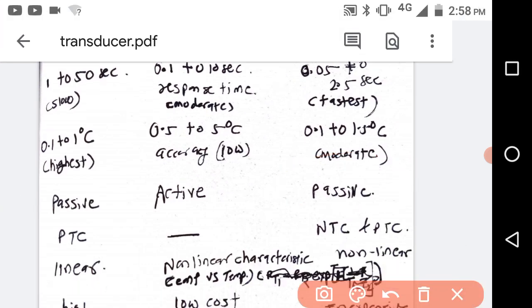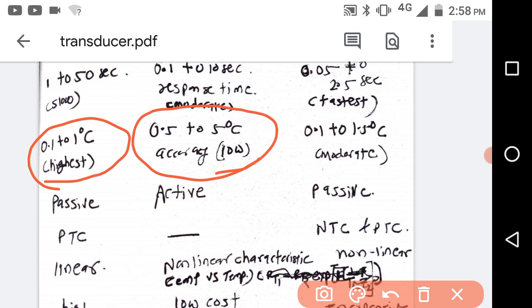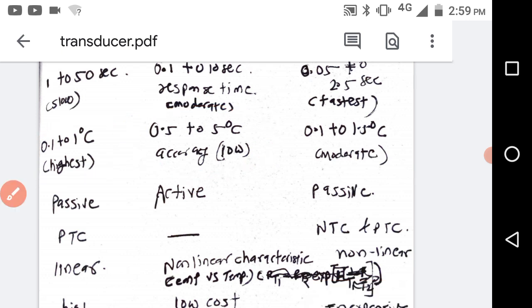So what is the accuracy? Accuracy is highest of RTD and it is lowest of the thermocouple. What is accuracy? Accuracy means the difference between the actual and the measured. So, what is that difference in case of RTD? It is up to 1 degree Celsius difference you will get. But in the thermocouple, it is 5 degree Celsius, and in the thermistor, it is 1.5 degree Celsius.